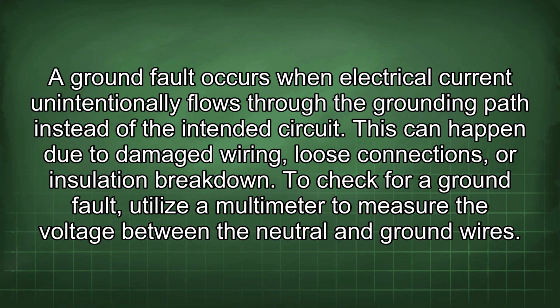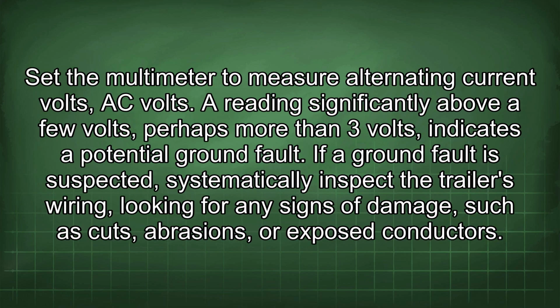To check for a ground fault, utilize a multimeter to measure the voltage between the neutral and ground wires. Set the multimeter to measure alternating current volts, AC volts. A reading significantly above a few volts, perhaps more than 3 volts, indicates a potential ground fault.